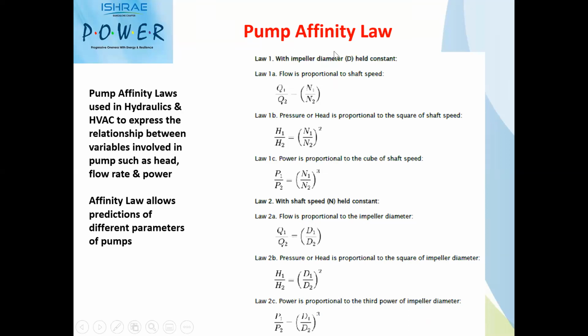So typically, when your diameter is constant and you want to vary the RPM, how does the flow vary with respect to your RPM? Q1 and Q2 are directly proportional to RPM, whereas head is proportional to the square of the RPM, and power varies with respect to the cube of the RPM. So when you have a variable speed application pump and you want to arrive at different flows and heads, theoretically you can use these formulas to arrive at different flows at different RPMs, different heads at different RPMs, and different powers at different RPMs.